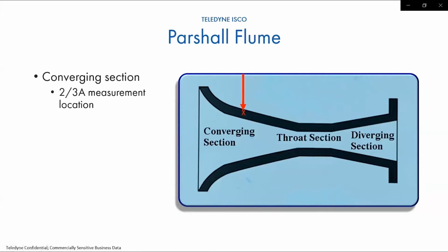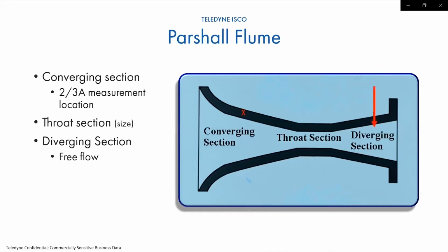And once again, in the ISCO Flow Data Handbook, we have some diagrams showing where the location is. But most of the time when you order your flume, you tell them what sensor you're going to put in there, and they're already going to put a staff gauge or possibly a stilling well at the proper location. Now the throat on a Parshall flume is going to determine the size of the flume. And then you have the diverging section, which is where you should see your free flow.